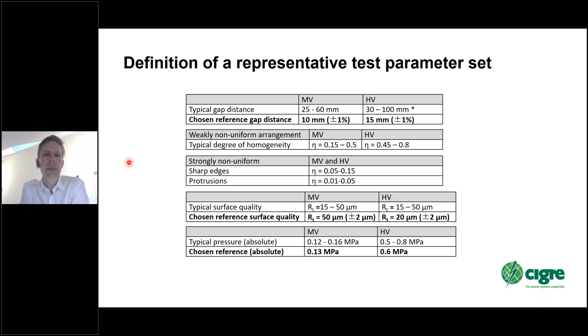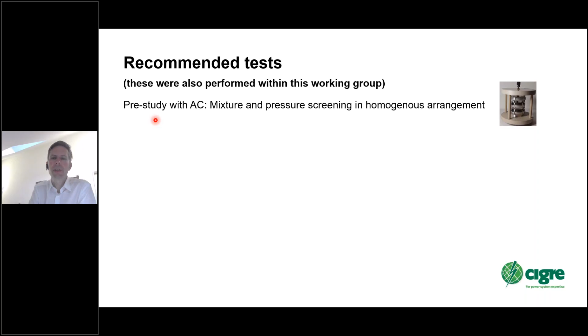So if we look into the different tests, the first three ones I will tell you now, those were the ones which the working group was also performing in the round-robin tests. A prerequisite or pre-study was done under uniform field with AC condition, just to make sure how the mixing ratio and the pressure screening is and which range of application we're working at and talking about. And then for the typical weakly and strongly non-uniform configurations, we actually went for these setups here.